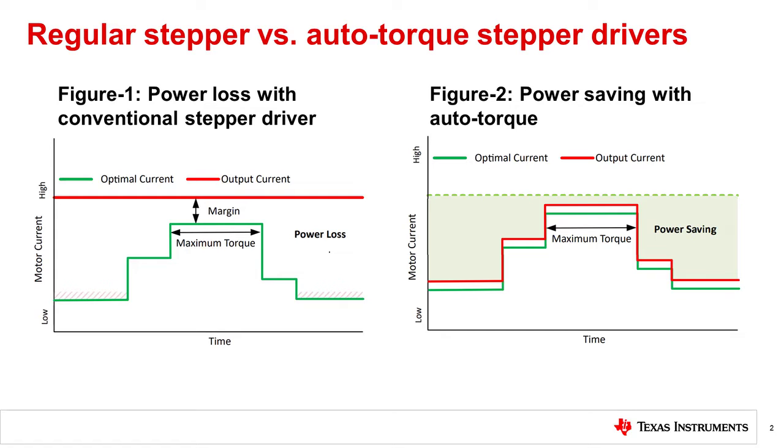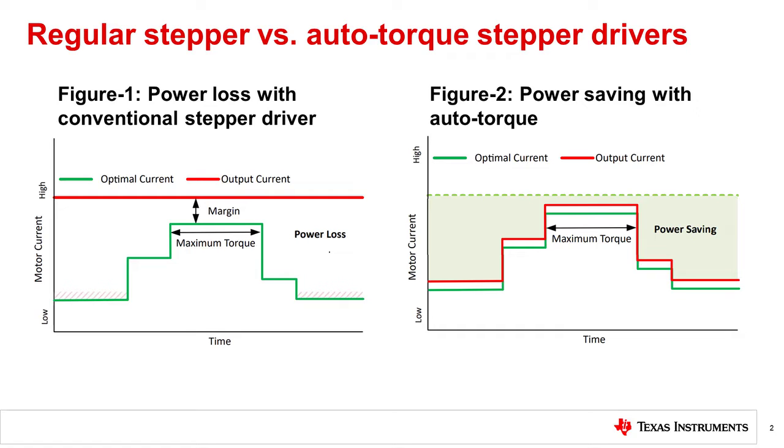However, in real-world applications, the motor may see a variable load torque, for example, with a load torque profile resembling the green line graph shown in Figure 1. Notice the motor is forced to output peak current all the time. This results with unwanted power loss during the durations the load torque is much lower than the peak torque. This power loss is translated to heat in the stepper motor and the driver and could lead to premature aging and failure of the components in the system.